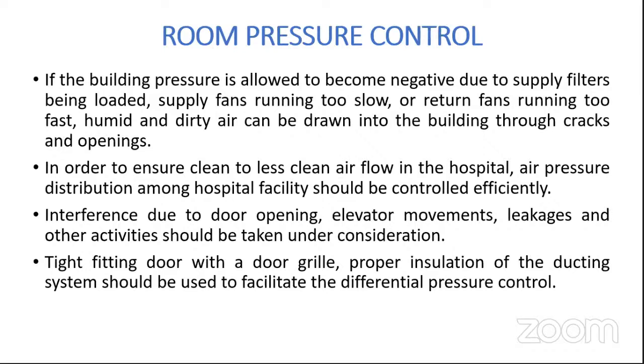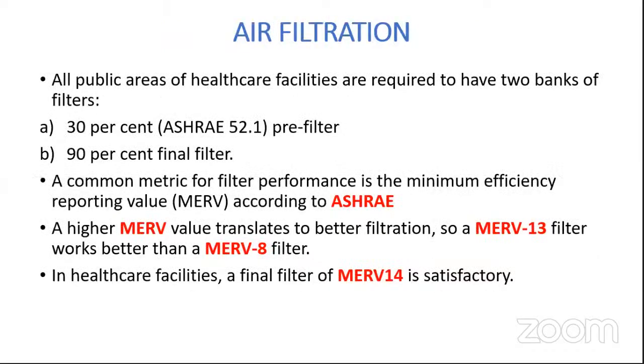In order to ensure clean to less clean airflow, air pressure distribution should be controlled. Where do we need what kind of pressure? We'll come to it in the next segment. When we are talking about leakages, that needs to be taken into consideration when we talk of pressure control. Now, according to ASHRAE, 30% of the air filtration is done by the pre-filter and 90% by the final filter.